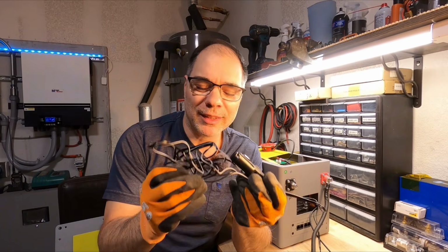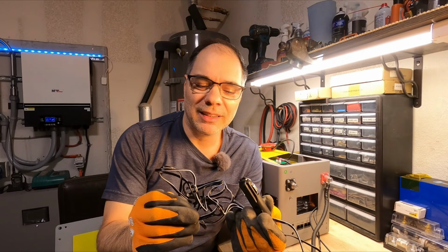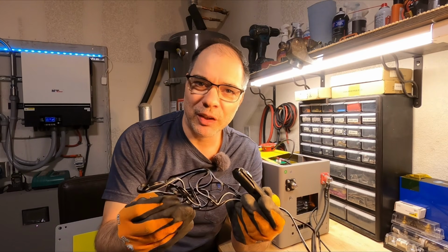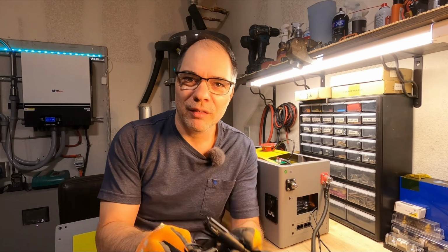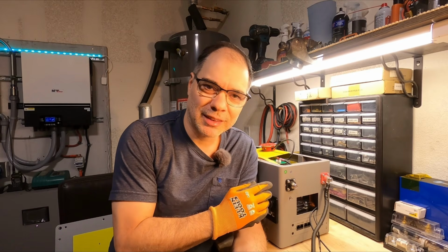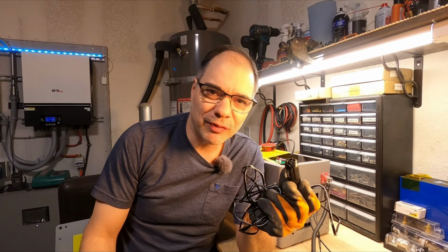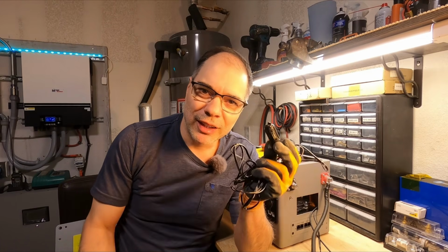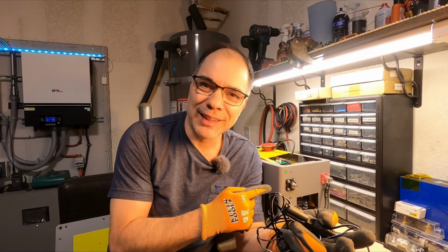So I think what happened there is this wire is so thin that it just ends up dissipating as heat, and it creates a high resistance scenario versus the terminals, which is a low resistance scenario, and that's what the BMS looks for in order to determine if it's a short circuit. Even though that 13 gauge wire could probably handle 200 amps just for a few minutes - just long enough to destroy your device. So if this was your device plugged into this battery, it would burn up before the battery did anything about it. So we need a fuse inside the battery on that small 13 gauge wire.